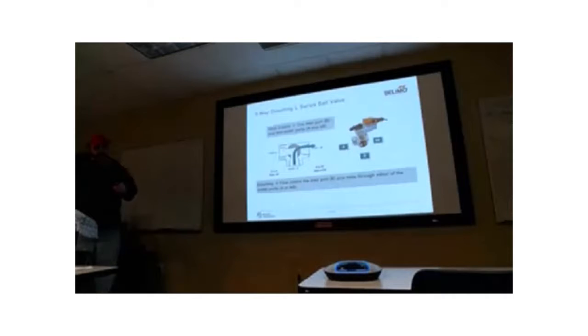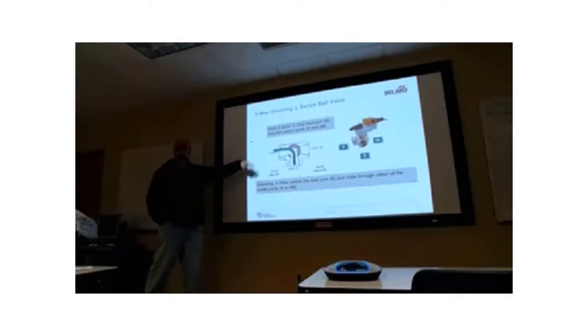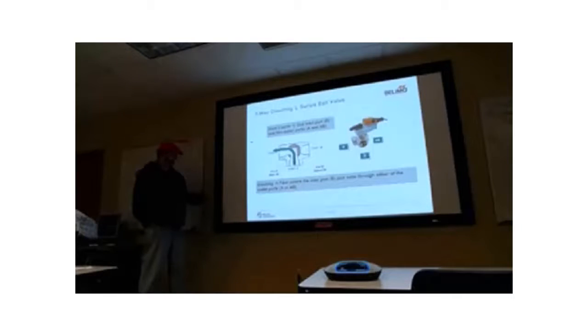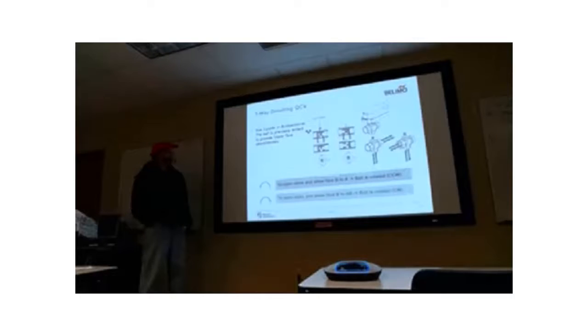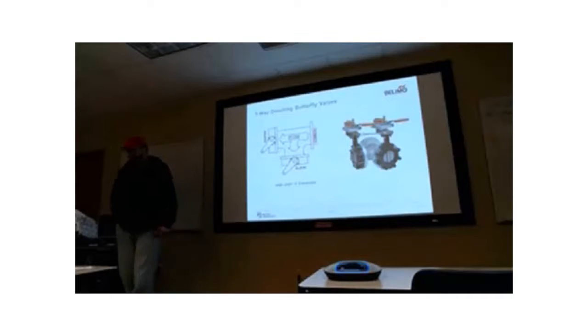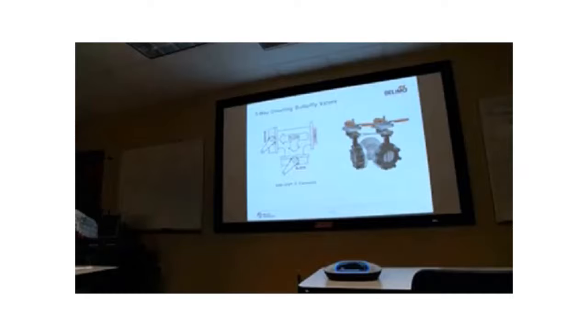This is one of the things where, as men, we're inclined not to read the instructions. But when you've got people putting stuff in for the first time, it's always good to read the stuff that comes with the valve, because it'll give you this kind of information. We actually had a situation downtown about 2 years ago where the new installation guys went through 40 coil installations before they figured out they were putting them in wrong, because nobody read the instructions.